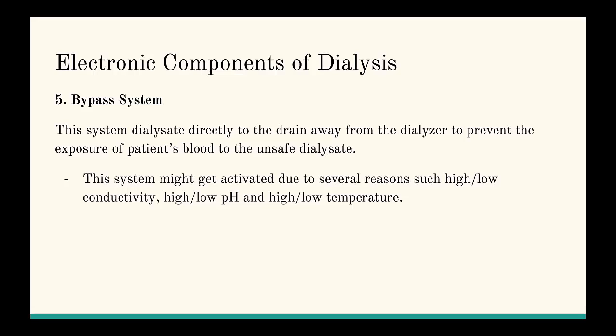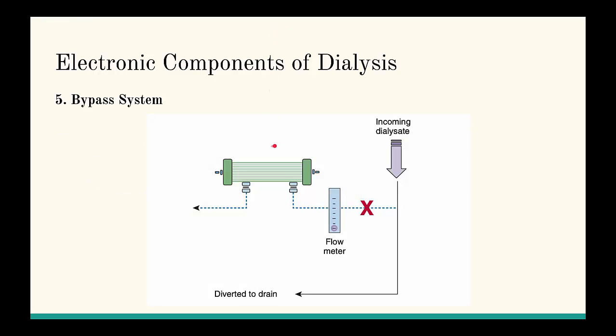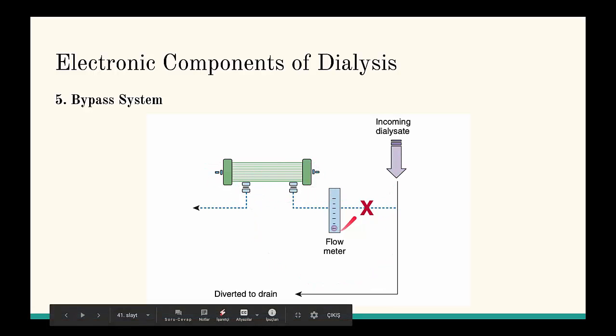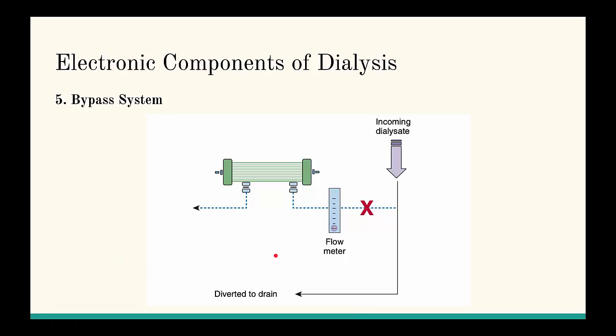So we have this other component, which is the bypass system. This is the system that's going to save you from getting hurt, getting harmed if there's something that's going wrong with the dialysis procedure. The other sensors that sense whether there's high conductivity, high or low pH, or high or low temperature, once they actually signal that there's a problem, then the bypass system basically shuts down the fluid. It takes it out from the regular circuitry, and it stops the machine from delivering you the problematic fluid so that you wouldn't get hurt. As you can see, the bypass system takes the dialysate and diverts it to the drain.